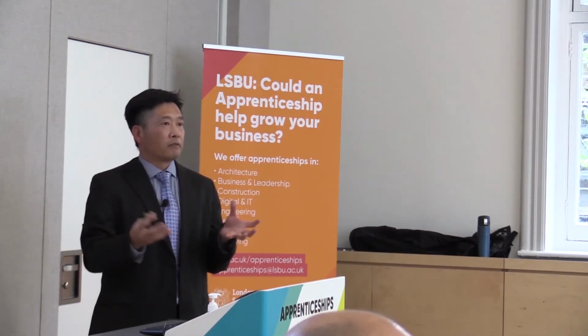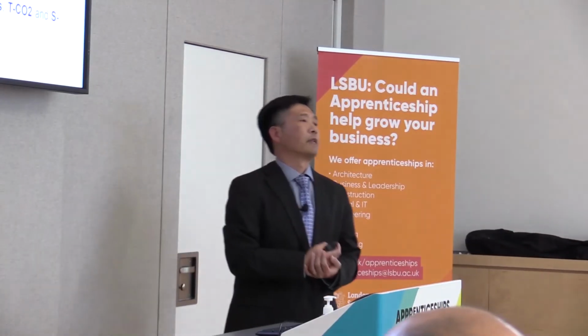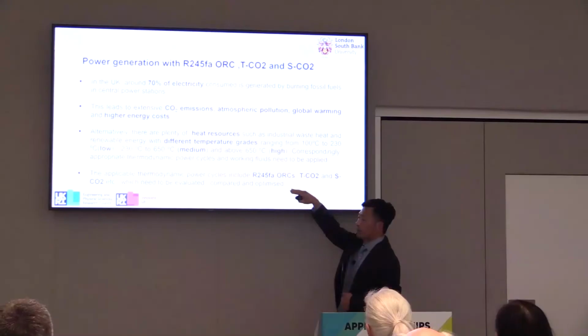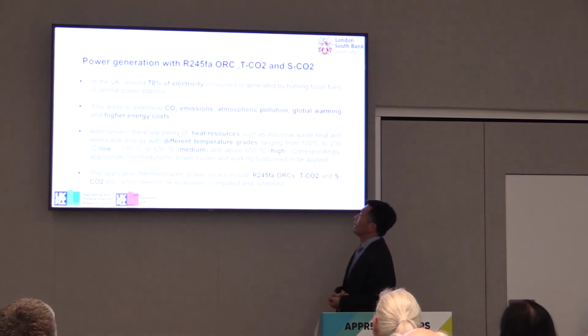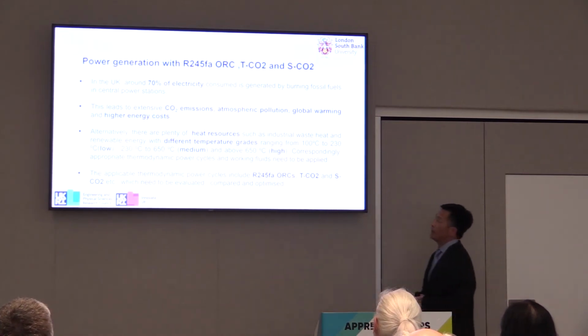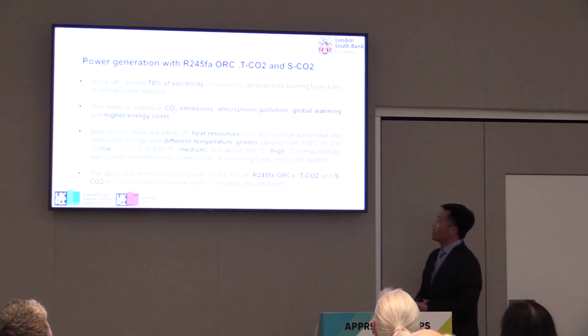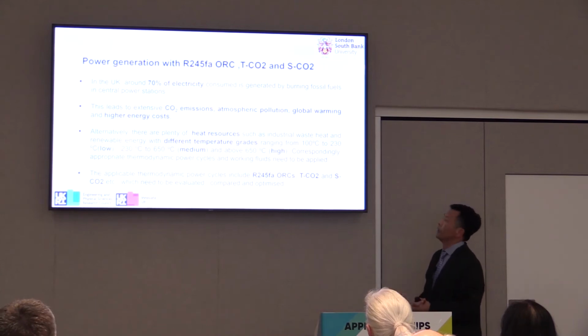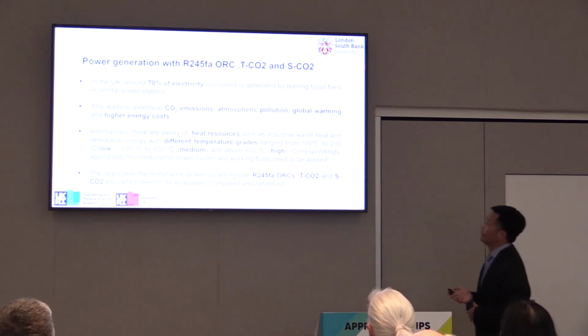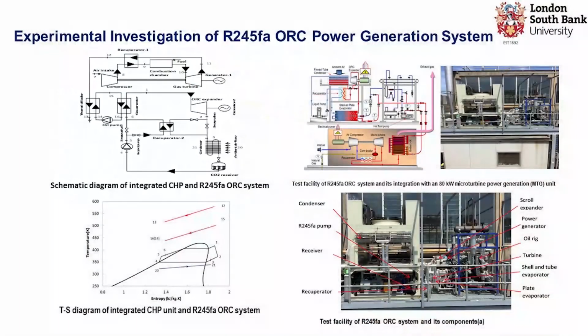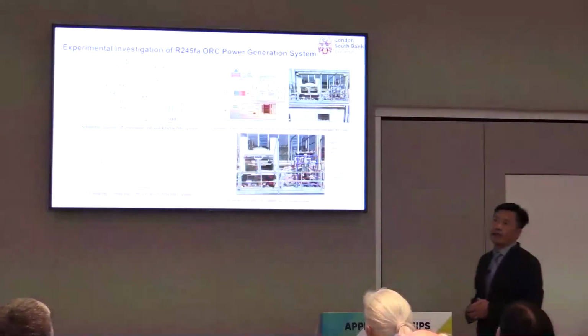To recover this waste heat at different grades, we need to utilize appropriate thermodynamic power cycles. That's why we concentrated on analyzing the applicable thermodynamic power cycles, including R134a and R245fa organic Rankine cycles, the transcritical CO2 system, and the supercritical CO2 system. For this CHP unit, we utilize the exhaust gas as a heat source, and we developed a new test rig for the R245fa organic Rankine cycle.